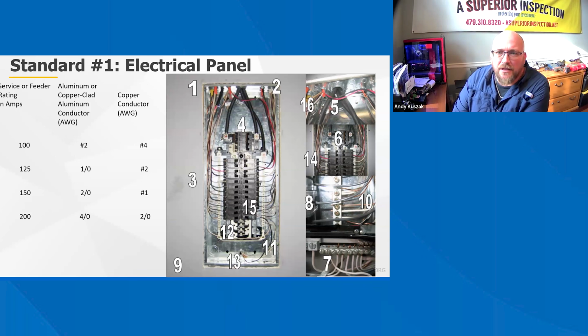And then on to number 5 over here on the top right-hand corner. Service entrance conductors must be protected from abrasion by the use of plastic bushings. Bonding bushings and jumpers are required to be used for metal conduits entering the panel enclosure through concentric or eccentric knockouts. It is often that you will find, especially on remodels, that you're missing a lot of those bushings or those connectors in the top of those panels. So keep an eye out for those.